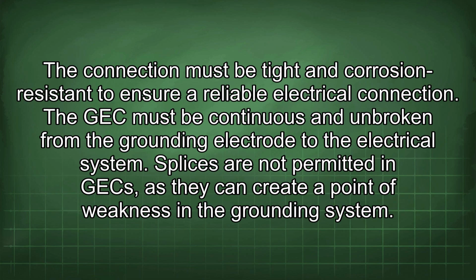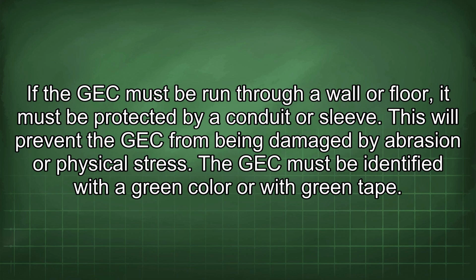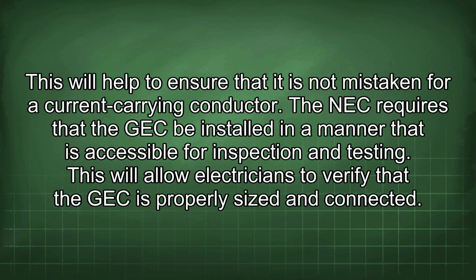The connection must be tight and corrosion resistant to ensure a reliable electrical connection. The GEC must be continuous and unbroken from the grounding electrode to the electrical system. Splices are not permitted in the GEC as they can create a point of weakness in the grounding system. If the GEC must be run through a wall or floor, it must be protected by a conduit or sleeve. This will prevent the GEC from being damaged by abrasion or physical stress. The GEC must be identified with a green color or with green tape. This will help to ensure that it is not mistaken for a current carrying conductor.